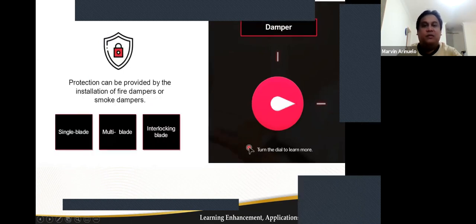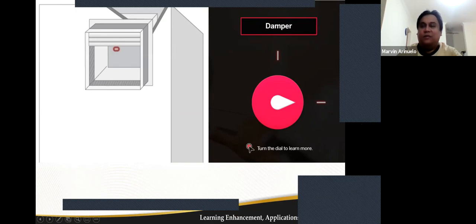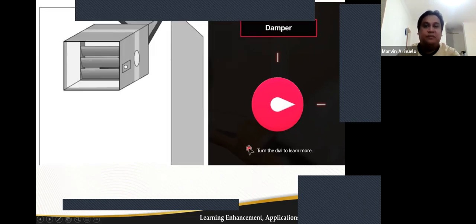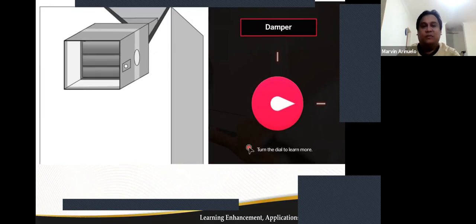Again, there is a material there that we call the fusible link, so that if it is met at a certain amount of heat, it will automatically shut off the damper to avoid the spread of fire or smoke from one area to another. It goes like this when it is at the shut-off phase. So a fire damper can control the combustion by closing and reducing the air supply. And this is how the motorized smoke damper looks like, but there should be an actuator somewhere.